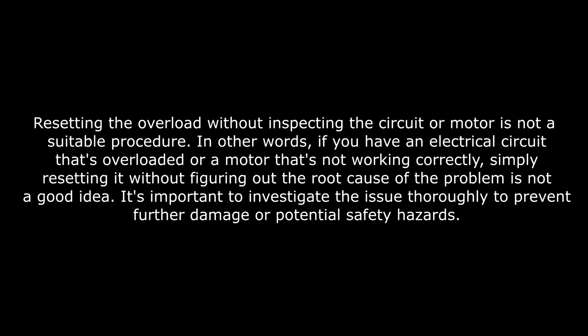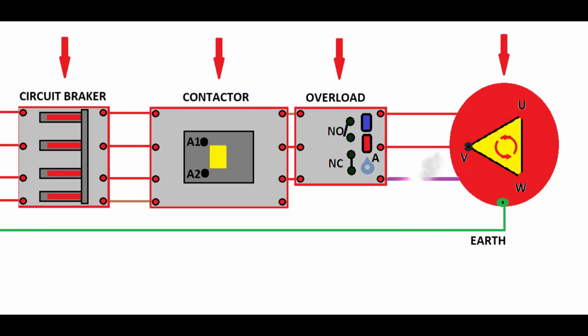You're supposed to investigate. Resetting the overload without inspecting the circuit or motor is not a suitable procedure. In other words, if you have an electrical circuit that is overloaded or a motor that is not working correctly, simply resetting it without figuring out the root cause of the problem is not a good idea. It is important to investigate the issue before you reset it. Also, setting the overload is a very important thing electricians must do, because if you do not set the overload correctly, you can burn the motor. So you have to pay attention to this.